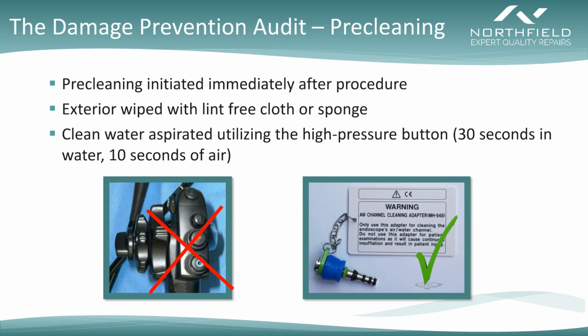That's where a lot of your clogged air water nozzles come from. So pre-cleaning has to be initiated immediately after the procedure. The specific steps will vary slightly based on the exact manufacturer and model number of your scope, but generally you need to see the exterior wiped with a lint-free cloth or sponge, and clean water aspirated using that high pressure button if this is an Olympus scope. Generally the rule is 30 seconds of water, 10 seconds of air, though it may be more or less depending on your manufacturer and specific model.